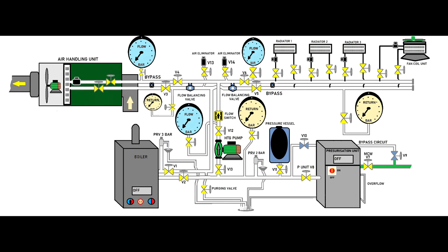If the system passes all the tests - the strength and the working pressure test - then I will open all the valves with the exception of the bypass that you can see on the pressurization unit. Of course people will ask me later on why I'm using the bypass and I'm not using the pressurization unit directly to fill the system.